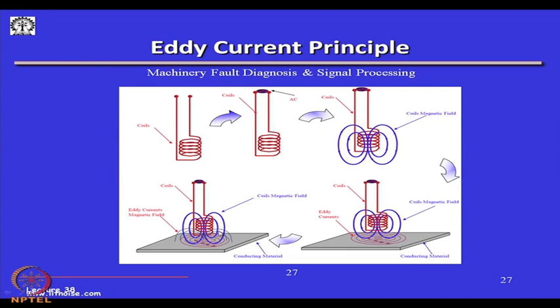By Lenz's law, the eddy current magnetic field will oppose the original field. If some way we can detect this difference in magnetic field — caused by eddy currents that are different due to a foreign inclusion, a defect, or a change in thickness — this gives us an indirect method to measure thickness, displacement of the coil from the conductive material, and so on.